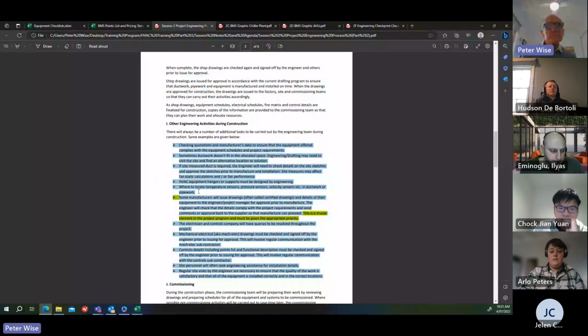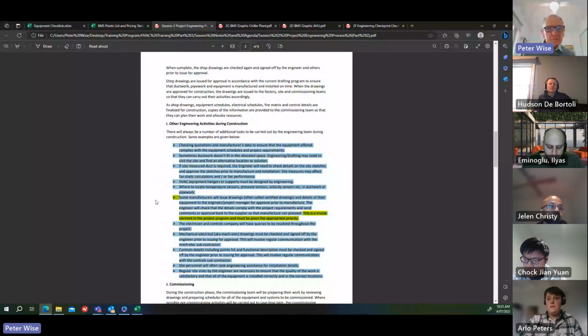The site team might ask you where to put temperature sensors, pressure sensors, etc., in the ductwork or pipework. Quite often with pipework, when that's being prefabricated, you might have to go to the factory and show them where you need the sensors. Some manufacturers issue drawings, often called certified drawings. So for chillers and air handling units, they might issue you a certified drawing to start manufacture, so that you then need to check them off and make sure everything's correct, because once they've been checked off, they're going into manufacture.